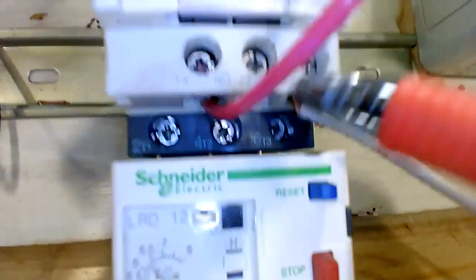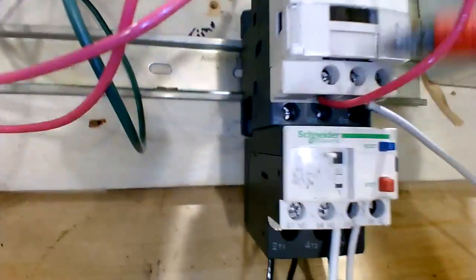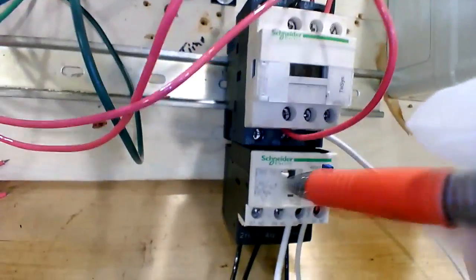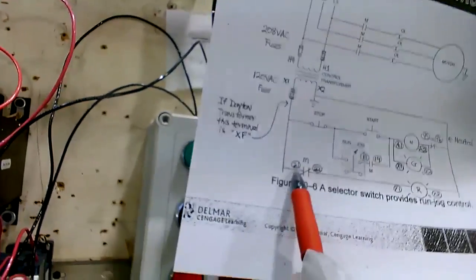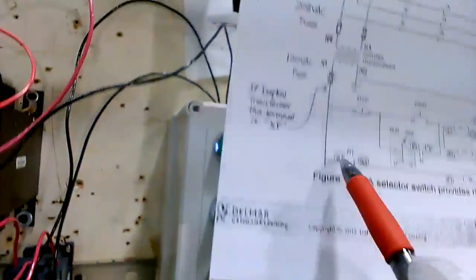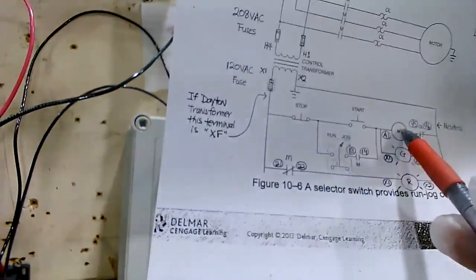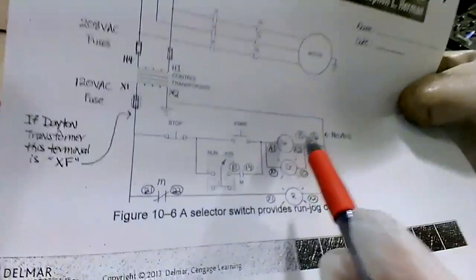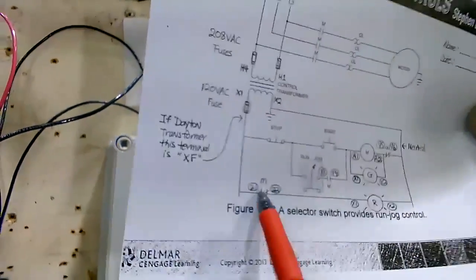You see 21, 22. It says NC for normally closed. See that? That's a normally closed contact, that one in the middle there, which means that when the starter is disengaged, those two contacts are touching each other, which makes a switch contact when the starter is de-energized. So you're going to run your power line, tap back up here for the fuse, and go to 21 on the front. And then 22 is going to run to the red light. It's also labeled M because of the coil. When that coil is de-energized, this will be made. When the coil comes on, this will open. So this is always opposite from this.